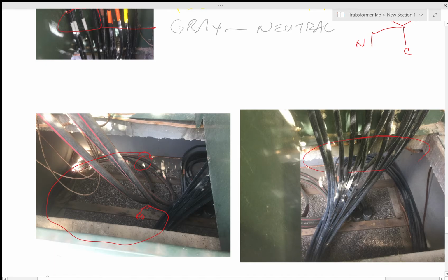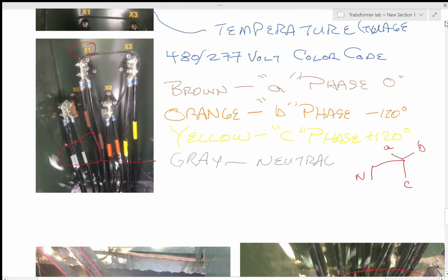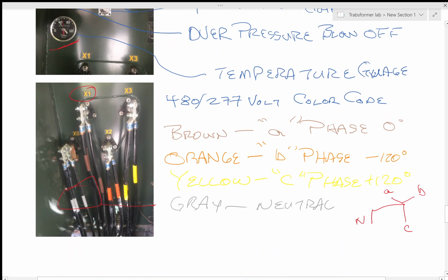Oh, something I did forget. On this low side, notice all the parallel conductors. What do we have? We've got 3 sets of parallel conductors. There you go. A parallel connection. Why did they parallel that stuff? Well, probably they used copper wire, and the bigger the wire, the more expensive it is. So I can run the same amount of current in 3 wires as I can in 1 bigger wire. So it's cheaper typically to run 3 conduits and 3 smaller cables than it is to run 1 big conduit and 1 big cable per phase. So you'll see parallel conductors, parallel phases of conductors in construction.